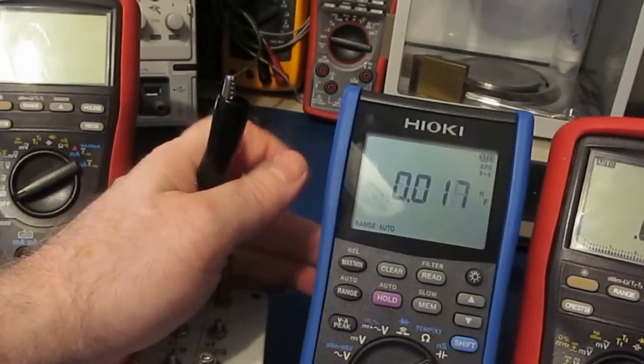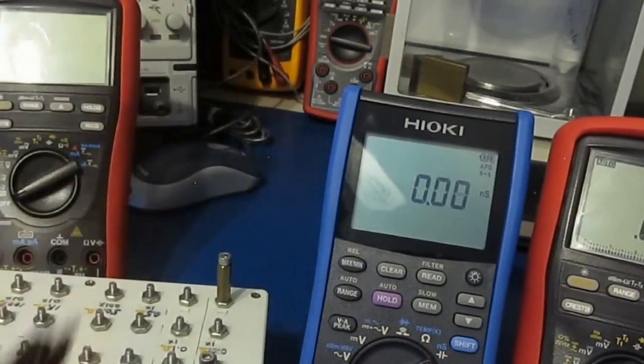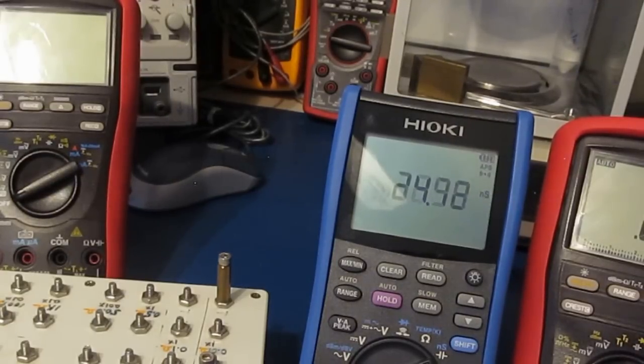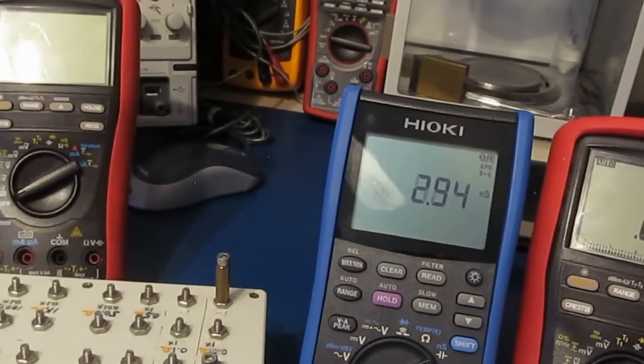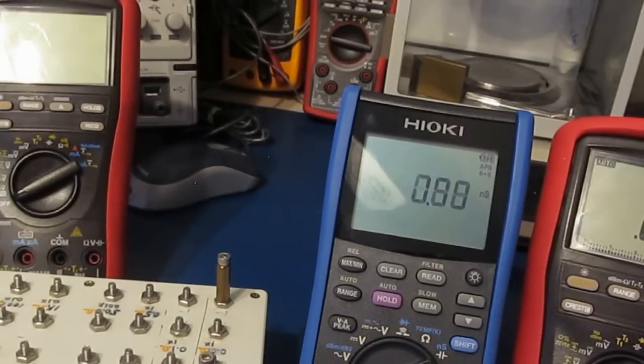Looks like we have to go to capacitance and hit the shift key. Yep, this is a 40 mega ohm, it should give us 25 nanosiemens. Yep, looks good. It's a 100 mega ohm, which will give us 10 nanosiemens. Looks good. And this is our 1 giga ohm; should give us 1 nanosiemen. Looks good—that's actually very fast.